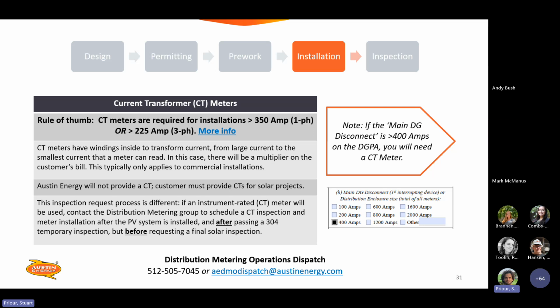So the inspection process is a little different. If you have a CT meter, you'll contact Distribution Metering Group to schedule a CT inspection and the meter installation after the PV system is installed and after passing a 304 temporary inspection, but before requesting a final solar inspection. So it's a little tricky. We're trying to basically mimic how main service revenue meters get installed. So what we'll do is we'll inspect the main PV switchgear before it's energized. So it's a safety thing, right? A lot of this stuff is safety stuff.